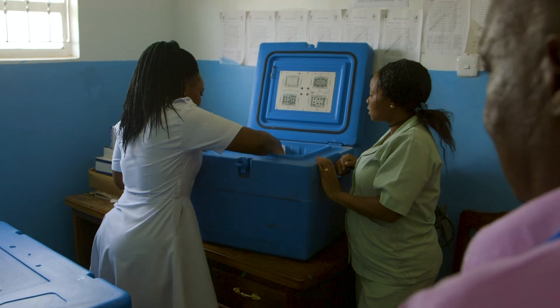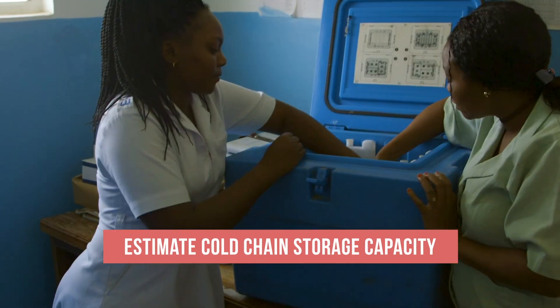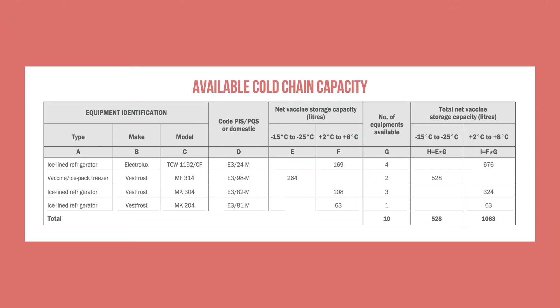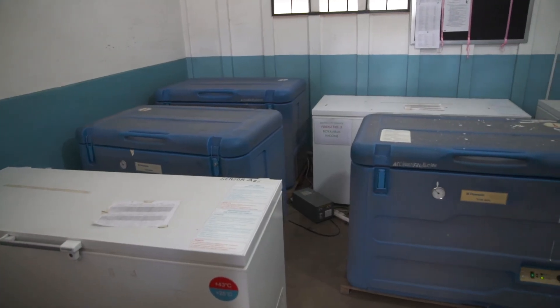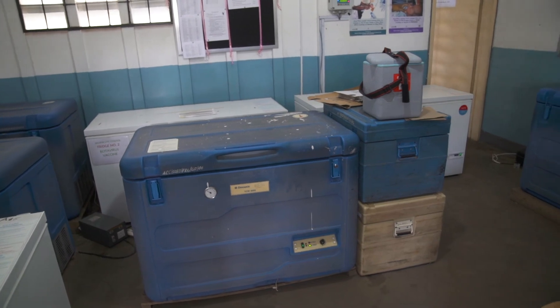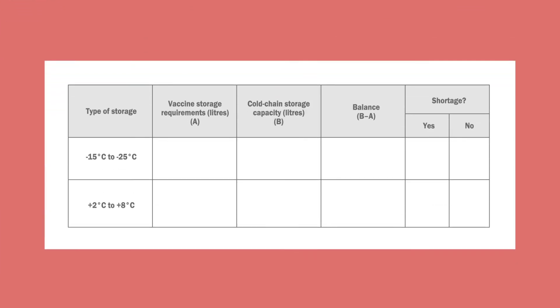Once you know your vaccine storage requirements, you will then estimate your cold chain storage capacity to determine if you have sufficient space. To do that, you can use a table like this one. You would calculate the total net vaccine storage capacity for each type of equipment, such as every model of refrigerator or freezer available, then add the capacities together to get the total net vaccine storage capacity for each temperature range. This calculation is covered in more detail in a separate video.